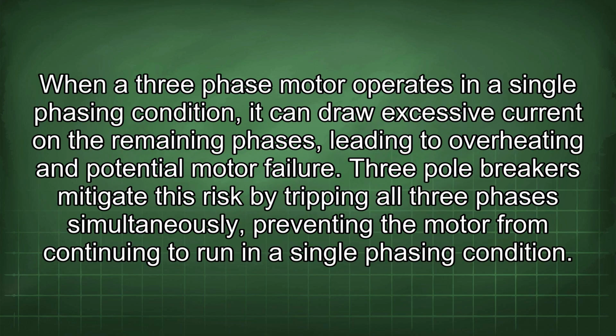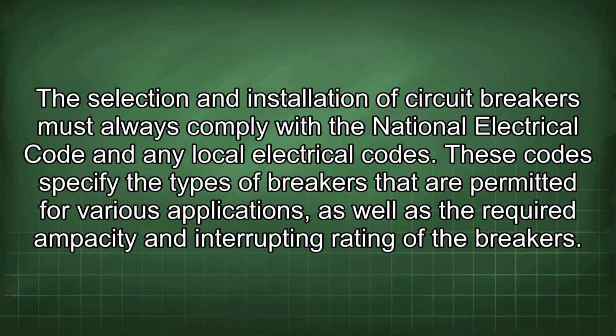When a 3-phase motor operates in a single-phasing condition, it can draw excessive current in the remaining phases, leading to overheating and potential motor failure. 3-pole breakers mitigate this risk by tripping all 3 phases simultaneously, preventing the motor from continuing to run in a single-phasing condition. The selection and installation of circuit breakers must always comply with the National Electrical Code and any local electrical code.